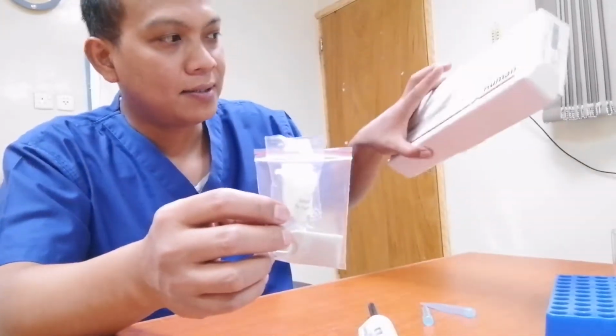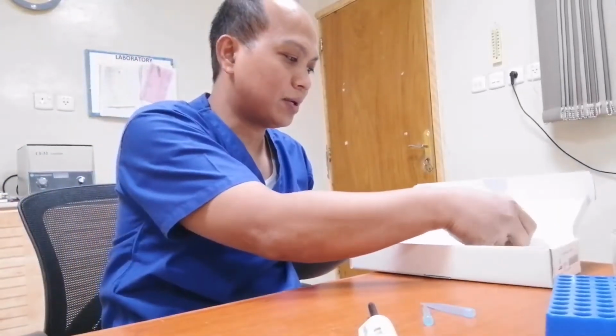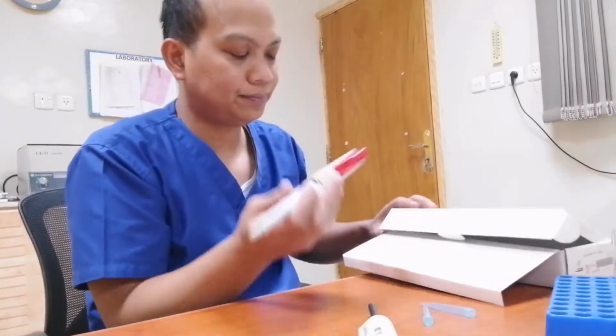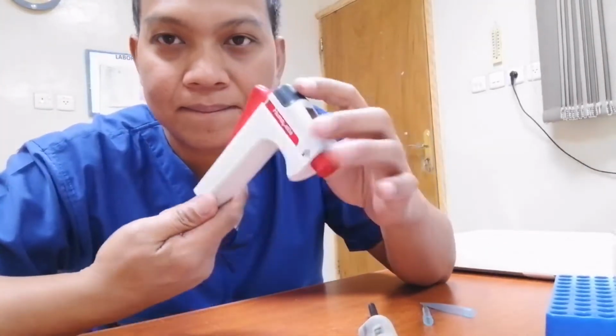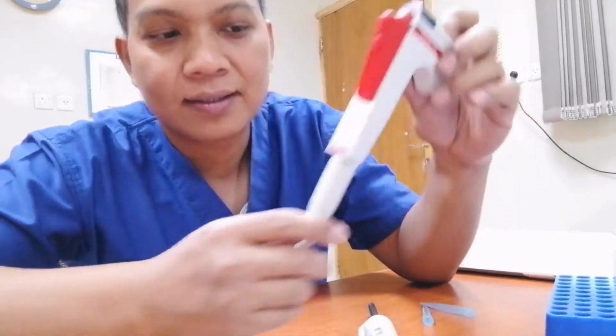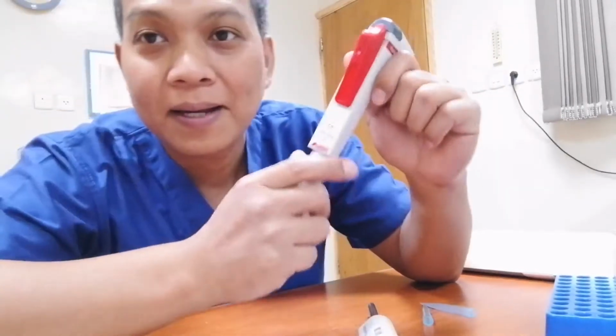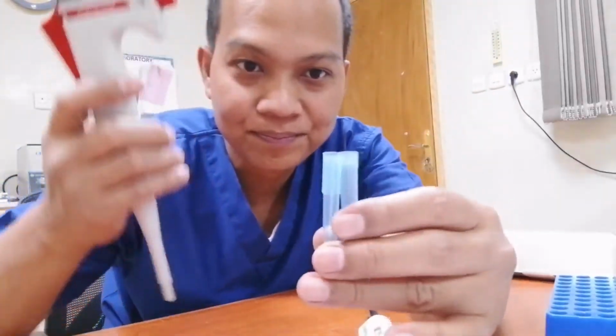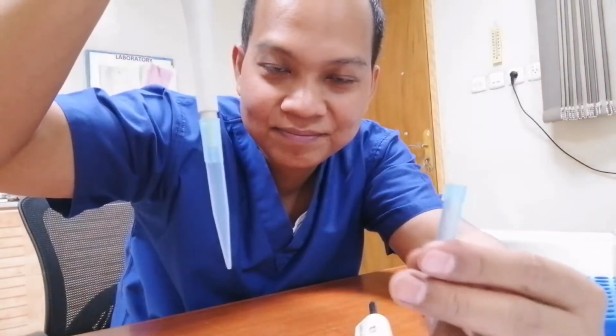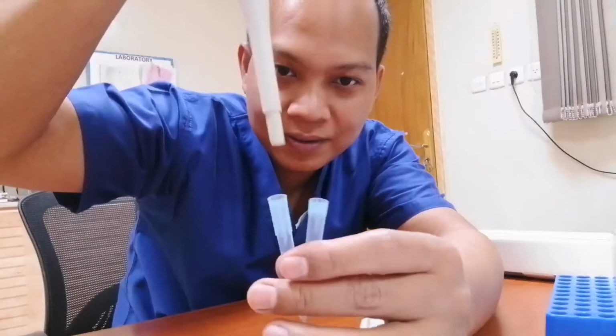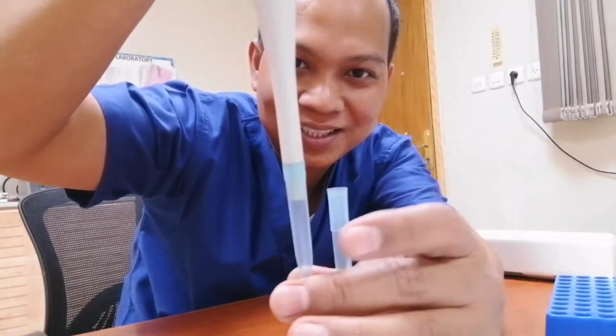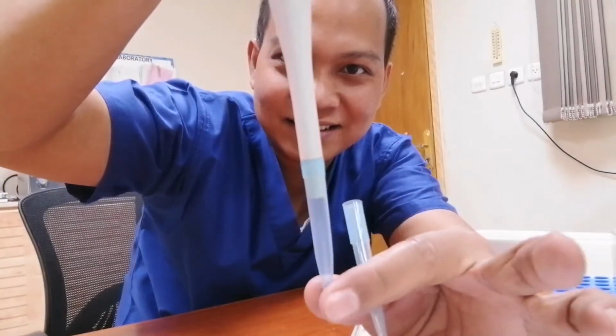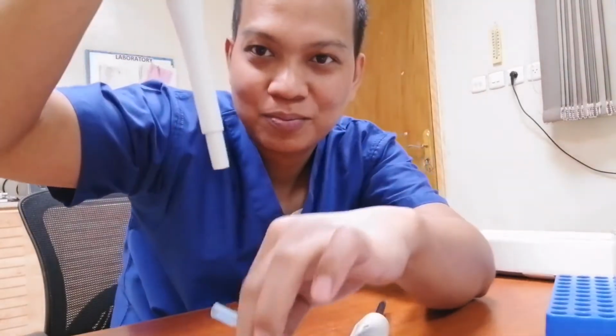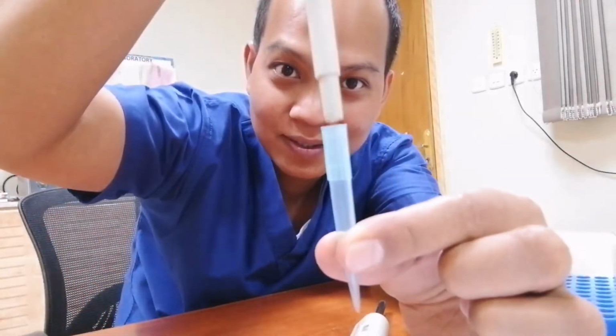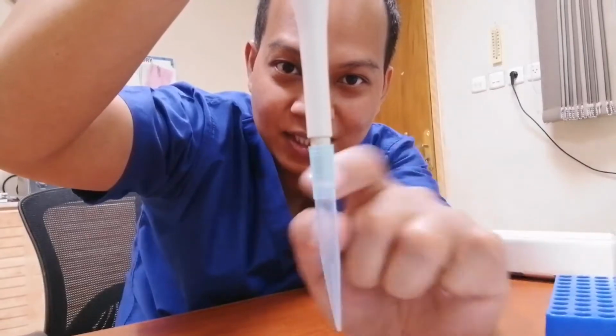So in this box of pipettes, actually we have here one pipette for Human. And if we are using this kind of pipette, the Humapet, it can hold 100 to 1000 microliter. The problem of this pipette is that this tip can only be used in these tips, but not in this tip. See, loose. As compared to this one, they are designed for these tips, okay? See the difference of the gap.